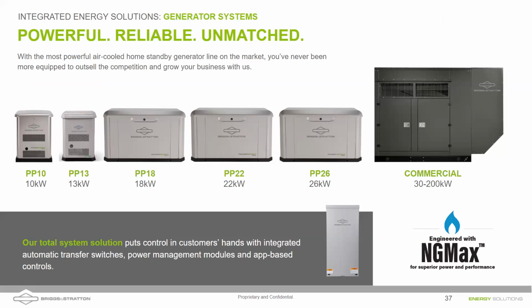A lot of times when you go out and say, I want a 22K generator, a 22 kilowatt generator, if you look carefully at the spec sheet, that 22K generator is actually rated on propane. And as soon as you go to run that same 22K generator on natural gas, it derates.